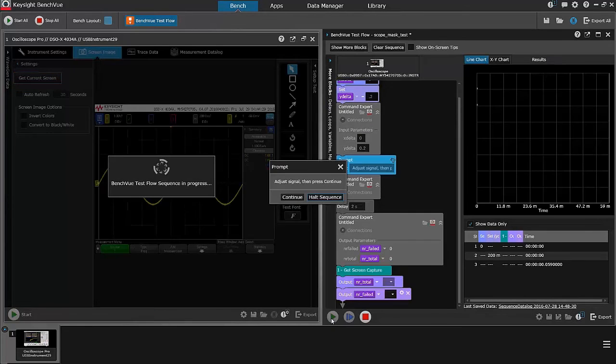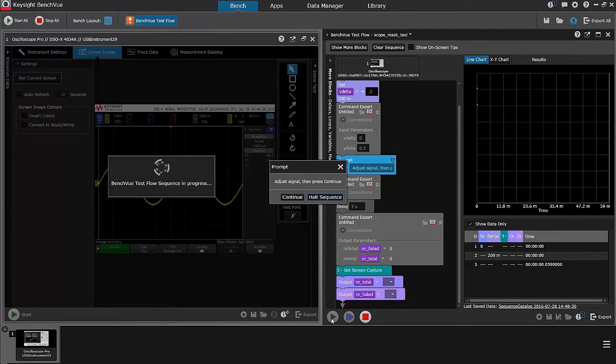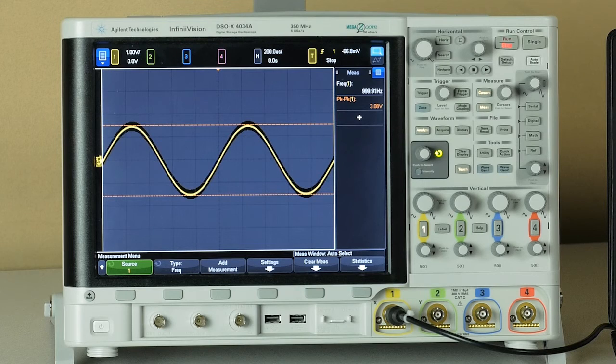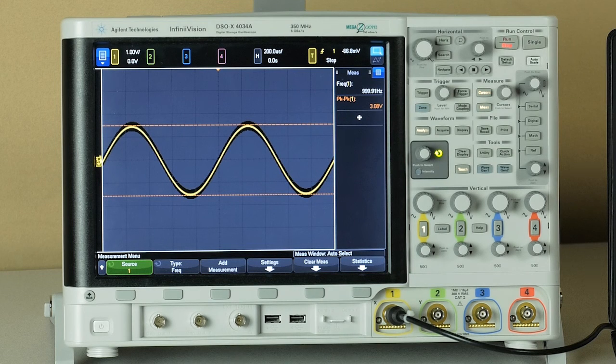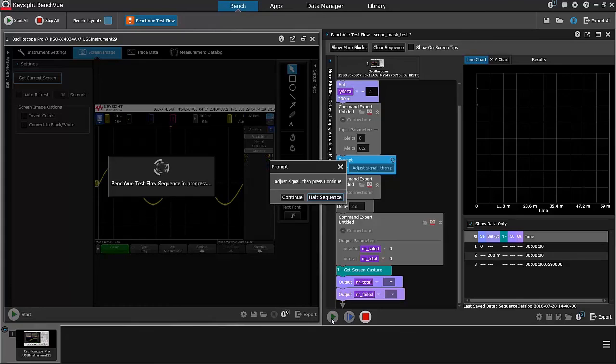When I hit run, the scope has captured the nominal waveform and applied the mask to it, which you can see on the oscilloscope itself. And what I'll do now is change the voltage and hit continue.